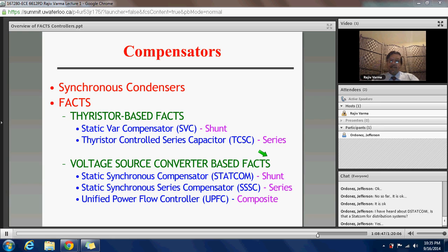Here again we have a shunt connected device known as the static synchronous compensator, STATCOM. Then we have a series connected device, the static synchronous series compensator, SSSC. And then you think, a shunt device does good, a series device does good, how about combining both to get the best of both worlds? When you do that, you develop a composite, unified device known as the Unified Power Flow Controller, UPFC. This is very powerful.